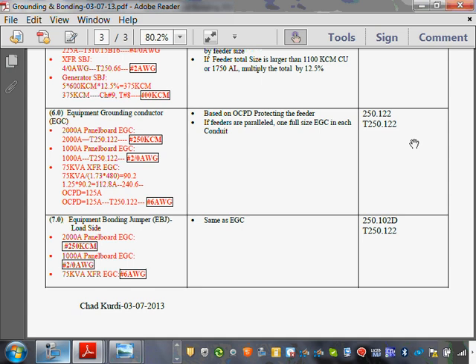Then you size the overcurrent protection device, 125. Now the code allows you to go higher than that, but typically, guys, if you size your overcurrent protection device for 125 and go up, and I ran, as an engineer, a lot of coordination curves for these, it will get you there. Though you can go higher than that. So I went to 125 circuit breaker feeding that transformer. From 125, equipment grounding conductor gets you number 6. So you have to size the overcurrent protection device feeding that transformer based on the amp size of that transformer, and 125 amp. You can go up to 250 though. Conservative here, and then the size of the conductor will be number 6.